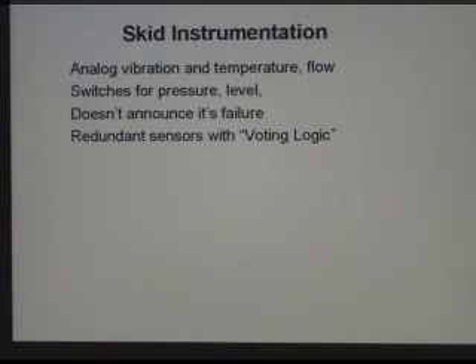Skid instrumentation. After the PLC was considered reasonably reliable and no longer the source of the majority of spurious shutdowns, they started looking at the skid instrumentation as the source of the majority of erroneous signals. So on the skid, we have analog signals for vibration and temperatures and flow rates. But we have switches, so digital signals, for pressures and levels.